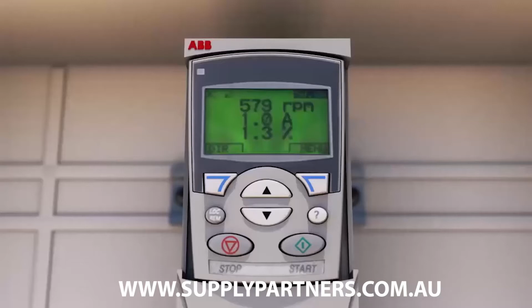So what I really want to highlight here is that for those of you who have heard about solar pumps, typically what that has meant to date is that a pump manufacturer that makes many different shapes and sizes of pumps has, for a very, very limited subset of their range, said, we can provide a controller, you put some solar panels connected to that controller, it runs that pump, therefore that's a solar pump. But the controller and the pump itself come as a kit from the manufacturer.